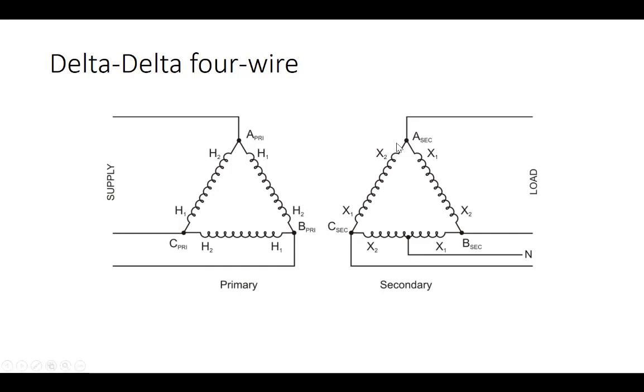What is unique about this connection is that the secondary has a tap in the center of the B to C transformer, which allows three-phase loads and single-phase loads to be fed from the secondary. Ordinarily, delta secondaries can only feed three-phase loads.